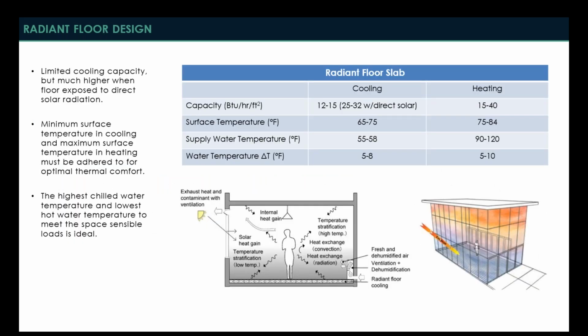So if we look specifically at radiant floor design, and in this case, radiant floor slab design, I have a table here that shows capacity, surface temperature, supply water temperature, and the water temperature delta T, which is essentially the difference between the supply and the return temperature.